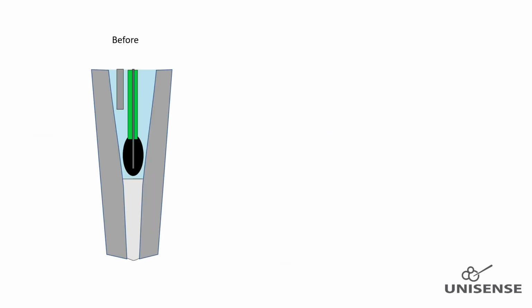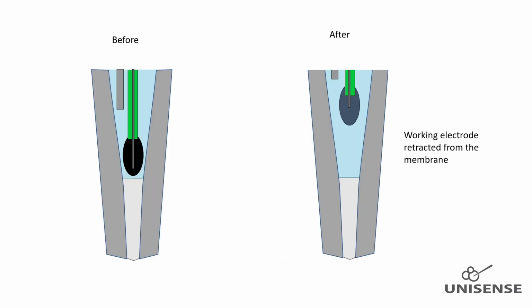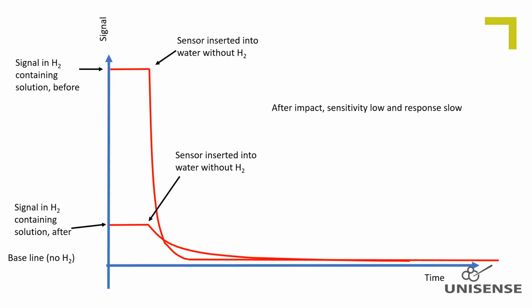If a sensor experiences a physical impact, like a drop on the table, the working electrode could be displaced. If the displacement results in a working electrode retraction from the silicone membrane, the signal will be slow and sensitivity low. The sensor will still work, but has lost its original performance. It is unfortunately not possible to restore original performance.